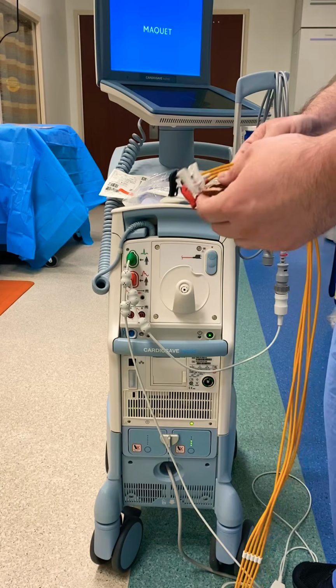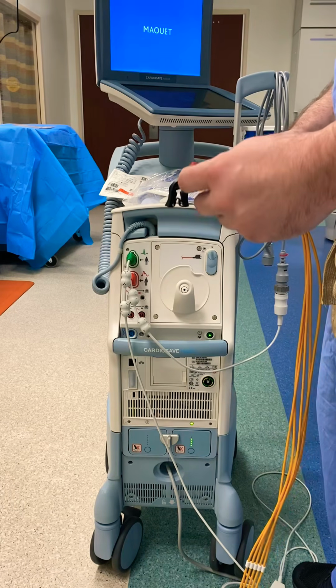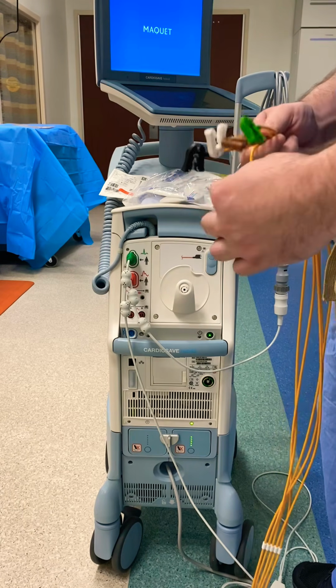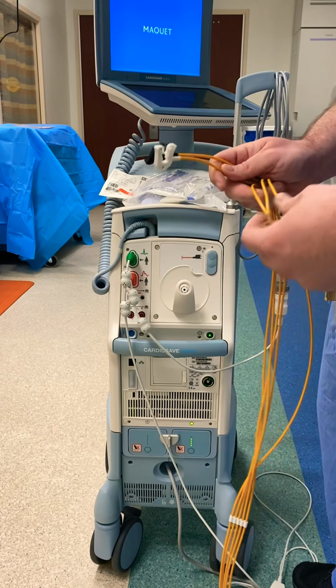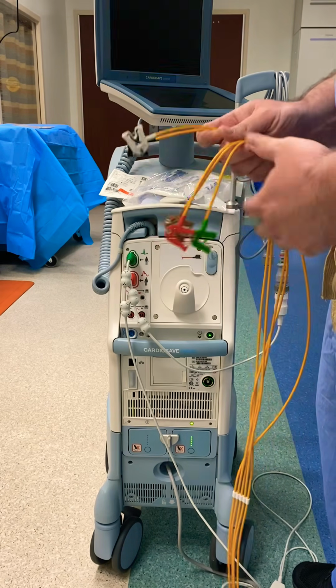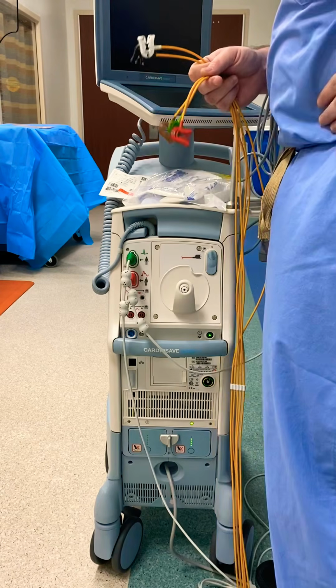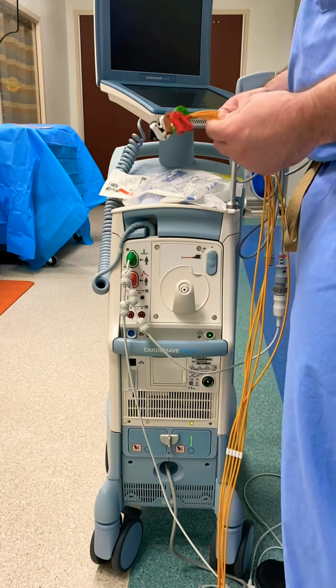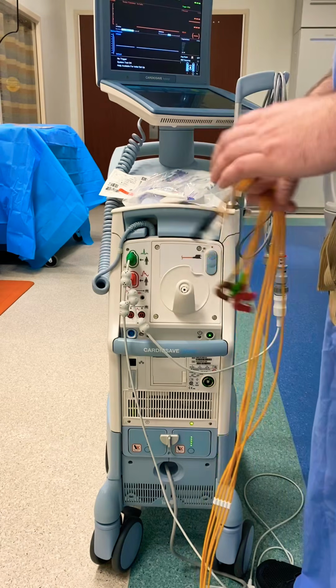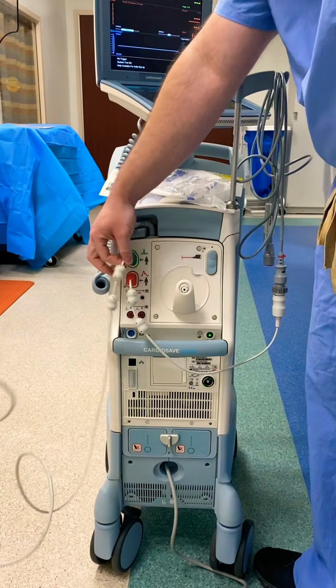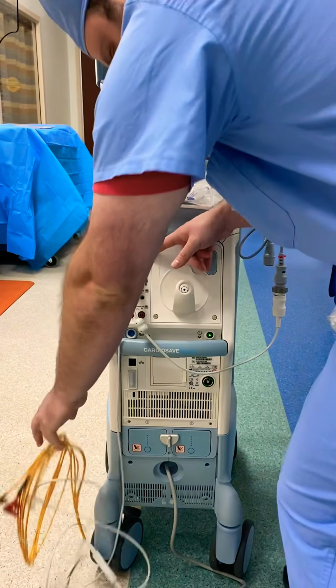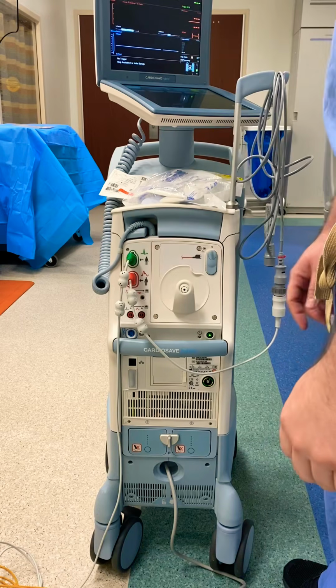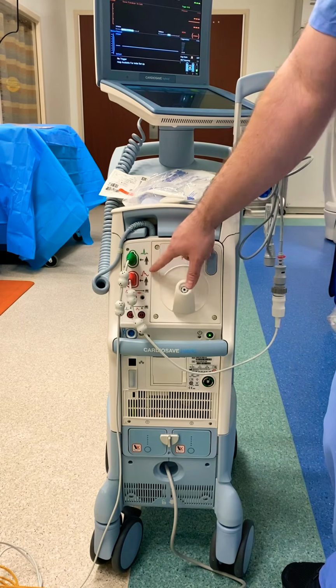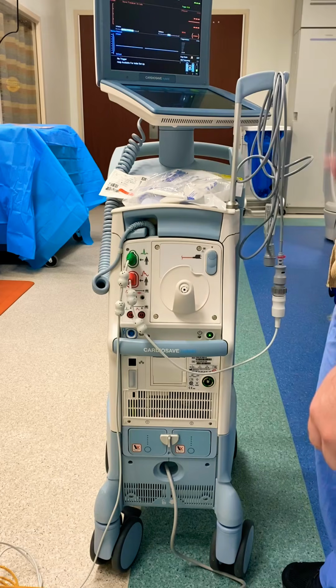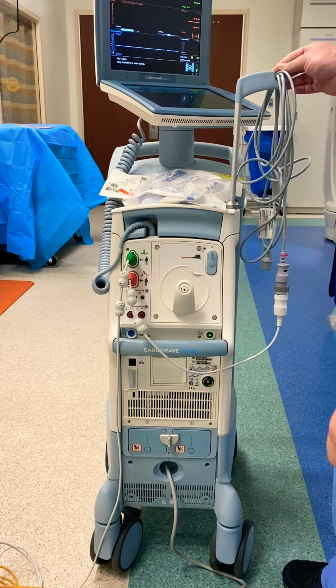While the case is still going on, make sure they're out of the way so they don't show up on x-ray and stuff. All of your white and your black, your left arm, right arm, will still go in the right spots. The rest of these three can go in the patient's left lower side down here. And be sure you put tape across all of them so that they're not pulled off, okay? So that'll be your EKG cable. It goes to this green plug-in over here that actually has a PQRS waveform. The red plug-in has an aortic pressure waveform, and that's what goes to your transducer cable.